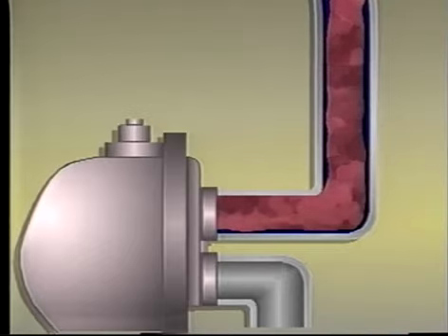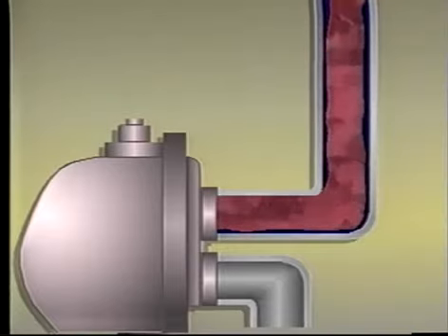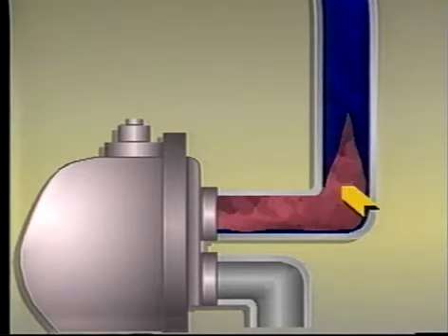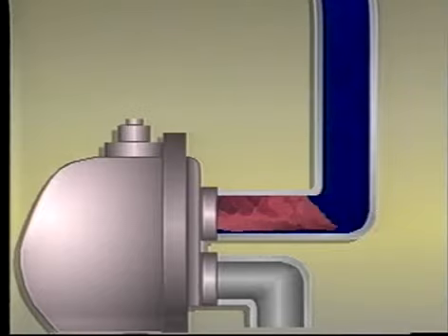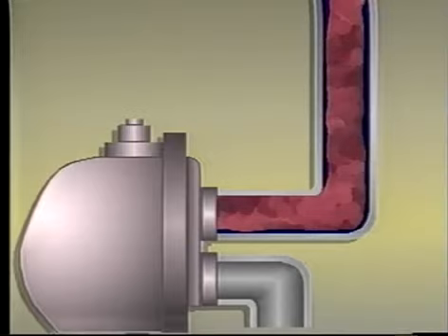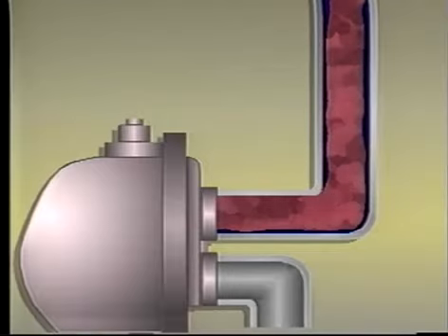The steam flow rate increases if a thermostatic element such as the bellows or wafer in an F&T trap opens. If a slug of condensate seals off the pipe, steam collapses downstream of the seal. Again, a pressure differential forms, and this, along with gravity, accelerates the slug. When this piston strikes the trap, it can damage a float, the thermostatic element, or other parts of its mechanisms.